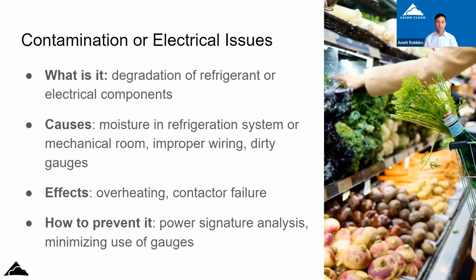The root cause of this can be moisture in the refrigeration system. So this can be non-condensables or moisture or water, improper wiring, or dirty gauges that can be adding, again, these non-condensables or other impurities into the refrigerant and oil system. Ultimately, this can lead to things like overheating and contactor failure, which will cause the oil to go bad, or get contaminated. What happens to oil when it gets too hot? It breaks down and loses lubricity. Okay, fair. So how can you prevent it? Power signature analysis, minimizing the use of gauges.